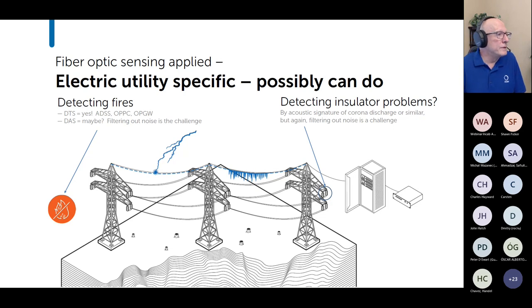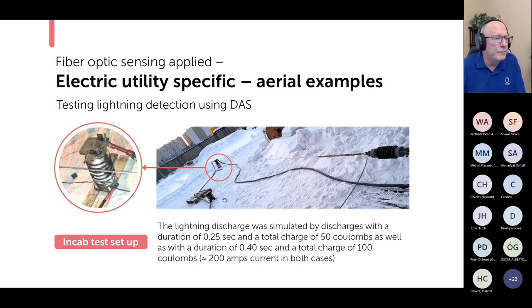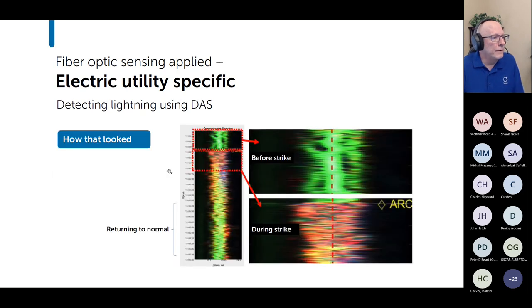We've done some testing on the lightning detection using DAS. This is just a test span that we set up outside of our factory in Perm. Very typical 50 coulomb lightning strike. And it worked. How that looks on the software used with these types of sensors is you get a signal before the strike, and then during the strike you have something different. That's what enables you to separate the two and say that something happened and generate an alarm. And then after the event, the signal returns to normal over time. For some reason, when I first saw this, it reminded me of the original Matrix movie, when they're looking at the Matrix on the screen. So this is giving you, you can see the Matrix.